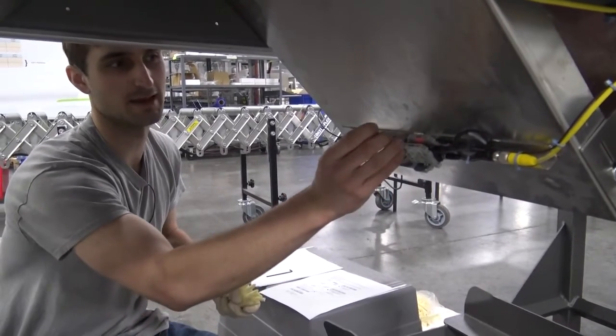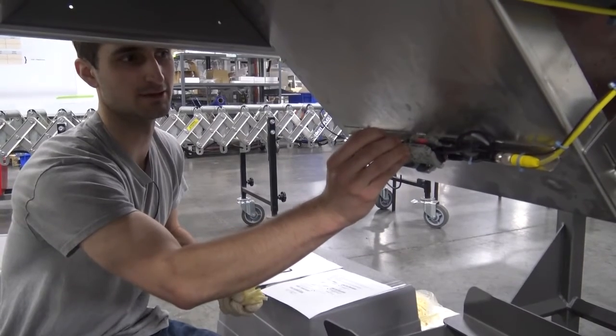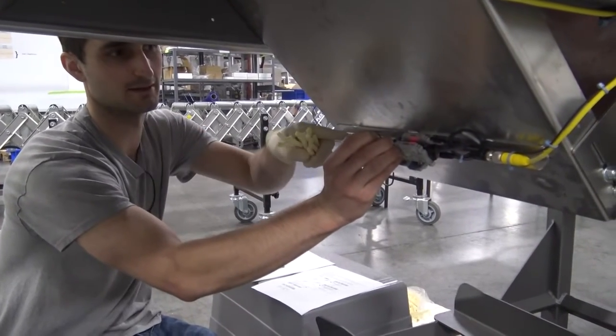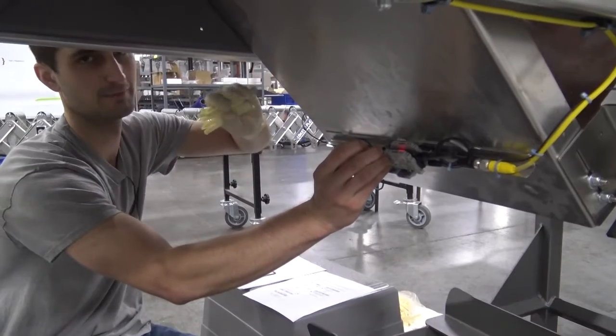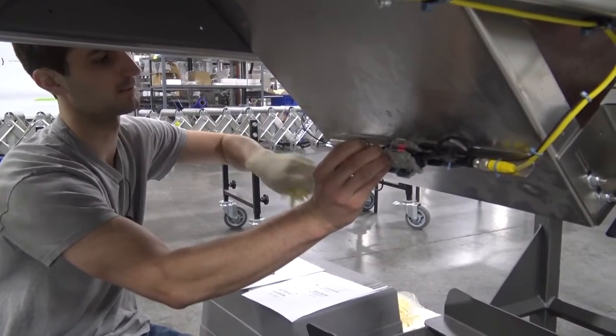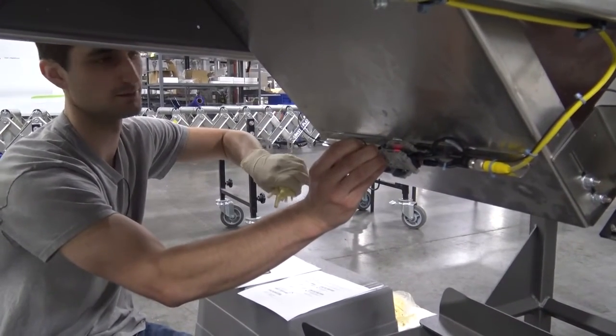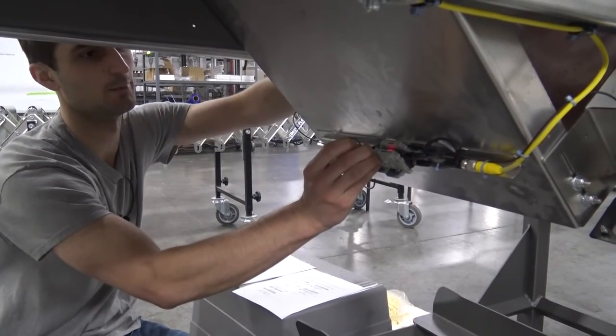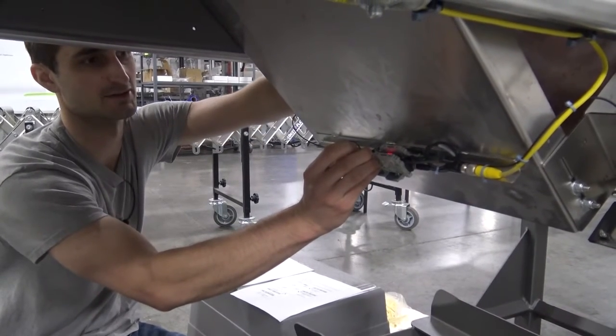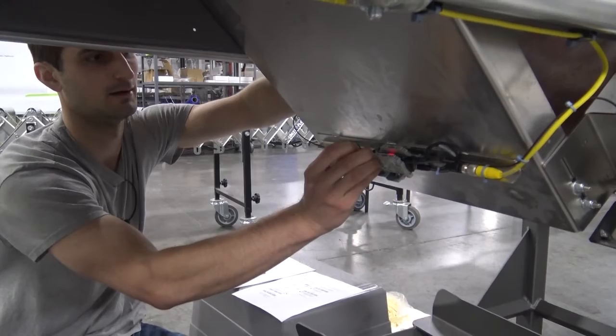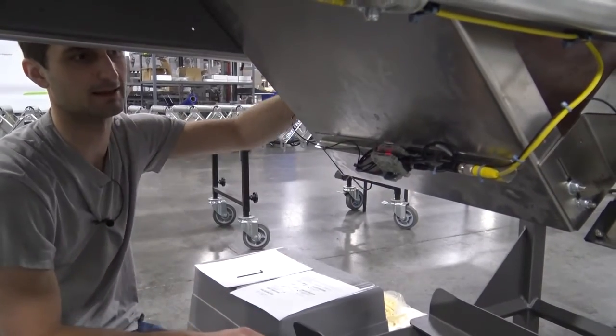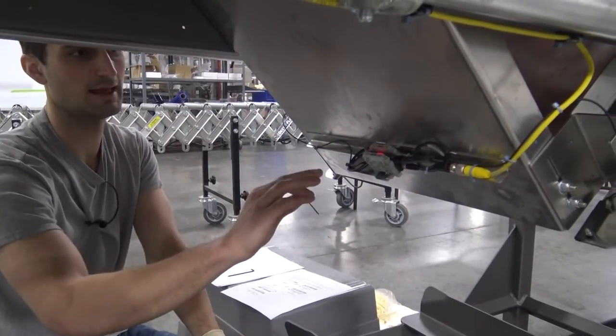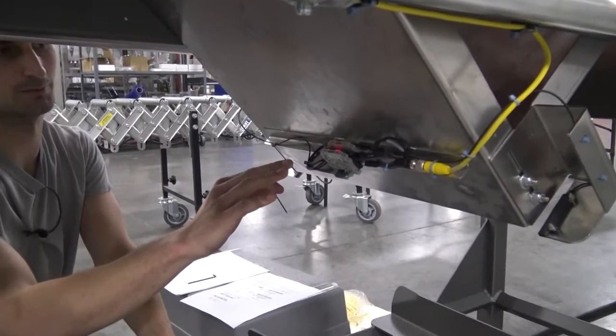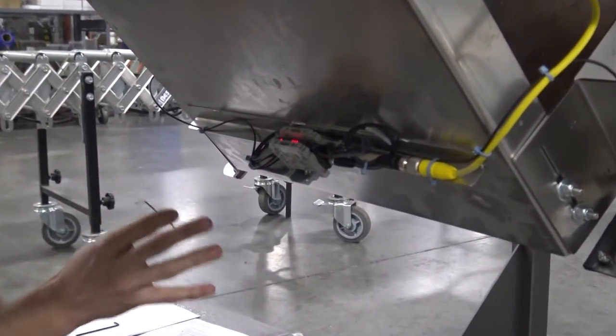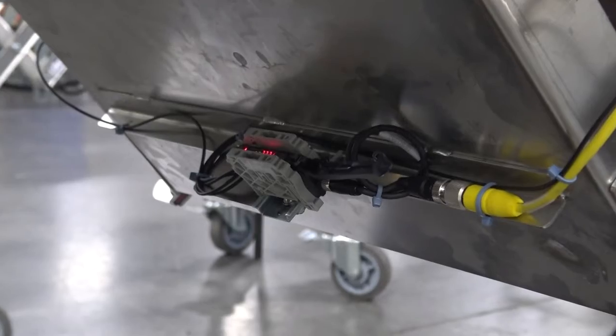Okay, so I'm going to hold the set button, and I'm going to continue to hold that, and I see the text set is blinking. I'm going to take my product and drop it so it passes through the sensors. And when I've done that, I'm going to let go of the set button. So I'm still holding it. I drop the product and I let go of the set button. And it gives me a calibration to the dynamic product. Okay, so I've done that.